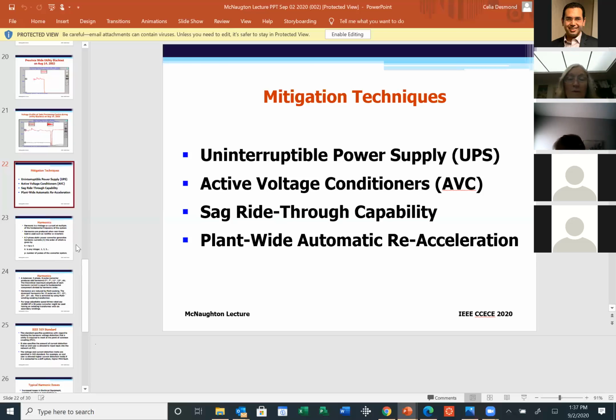However, the advantage of active voltage conditioners is that you can protect a much larger area. So if you have an industrial site or a facility that provides a very critical service, you can zoom in on a section of that plant that is the most sensitive and install active voltage conditioners. These devices have been around, I'm going to say, for at least 10 to 20 years.